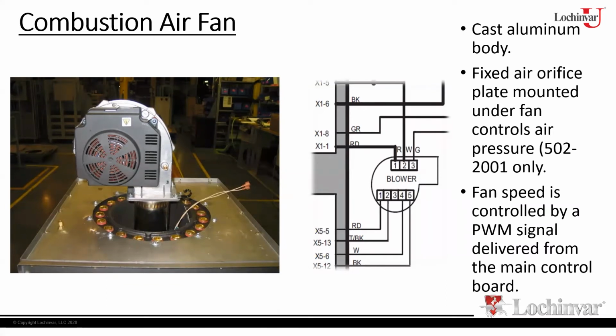Now, the fan is being monitored by the control module. So the control module will send a signal out. It gets a signal back. And basically, that return signal has to be within 30%. So basically, it's monitoring what the fan is actually doing. So if for some reason the fan is not operating as it should, the unit will sense that and then go into a lockout, and you will see either fan speed high or fan speed low lockout. And we'll talk more about that in a second.